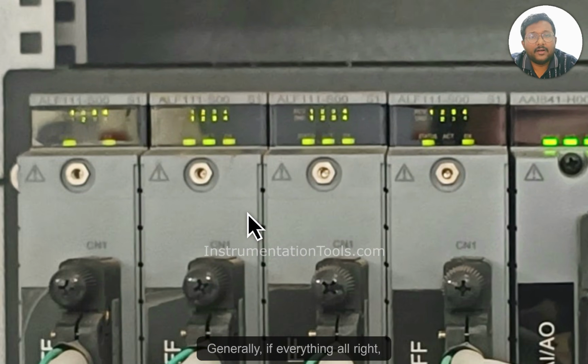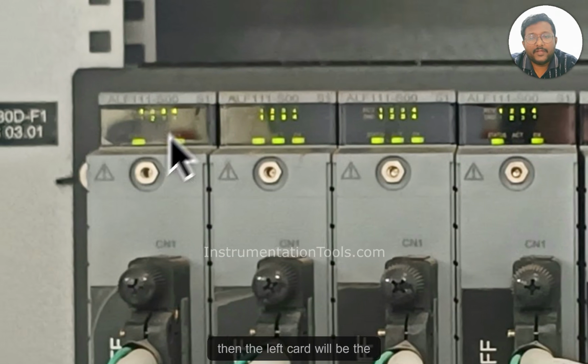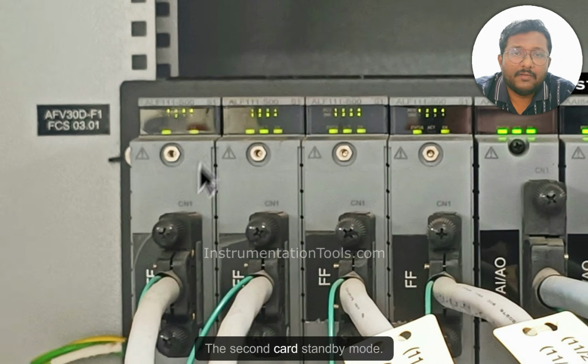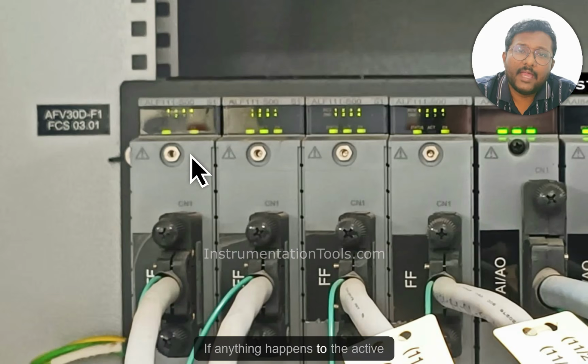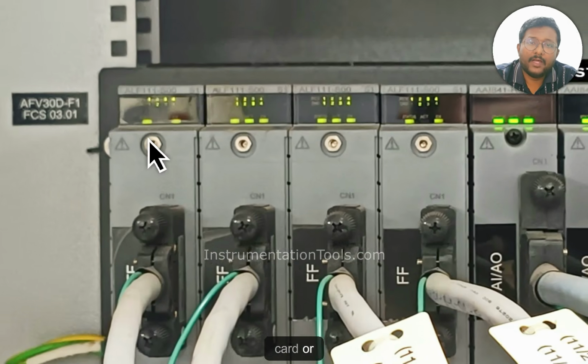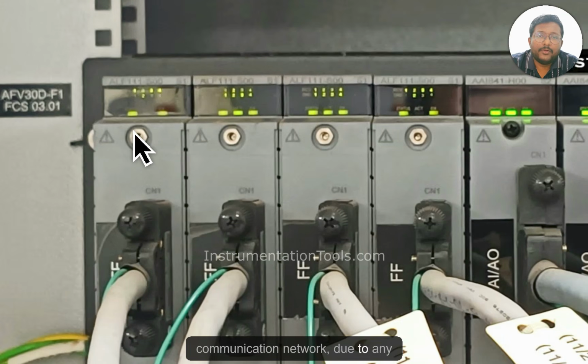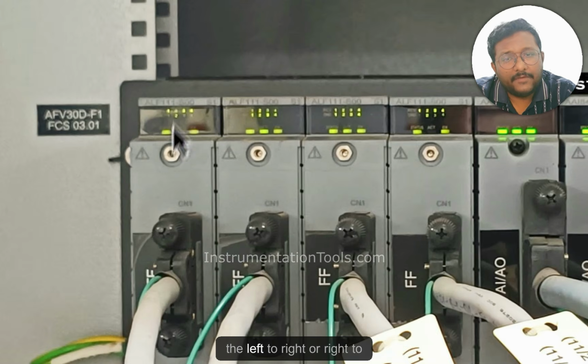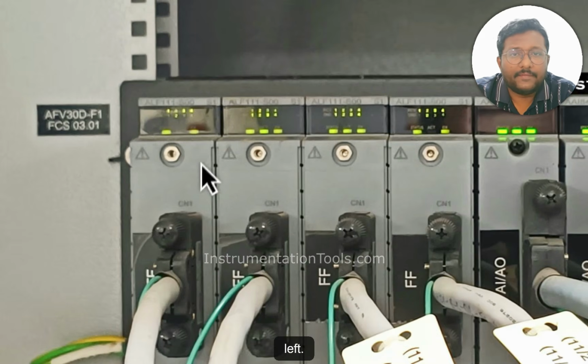Generally, if everything is all right, then the left card will be in charge. The second card is in standby mode. If anything happens to the active card or the communication network due to any issue, then the control will change from left to right or right to left.